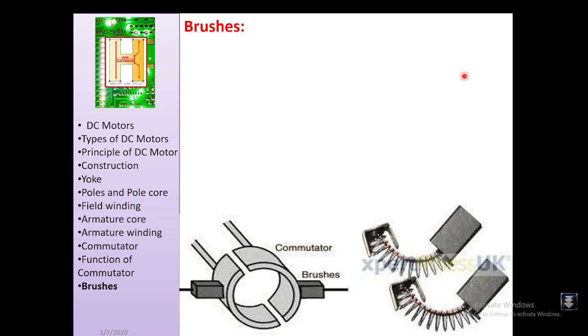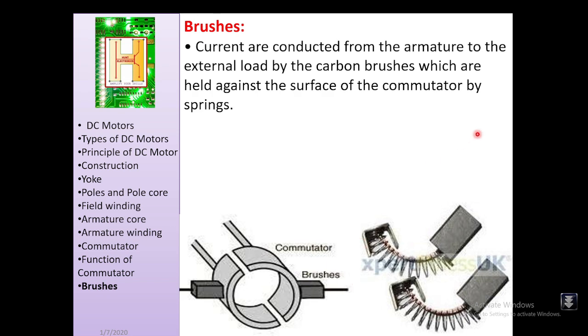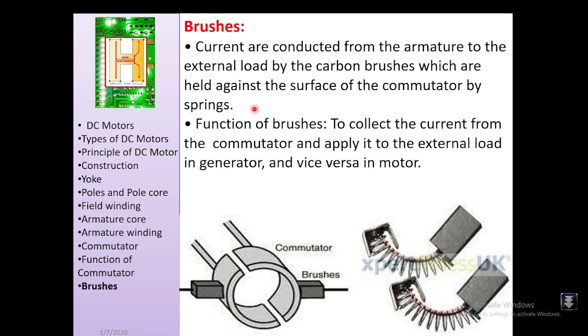Brushes are held against the surface of the commutator by springs. They conduct current from the armature to the external load, or from the external load to the armature. In generator mode, brushes collect current from the commutator and supply it to the external load. In motor mode, external current is supplied through the brushes to the commutator and then to the armature. Brushes are generally made of carbon and are rectangular in shape.